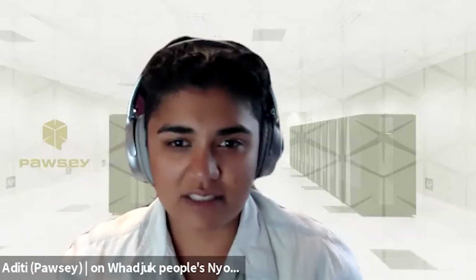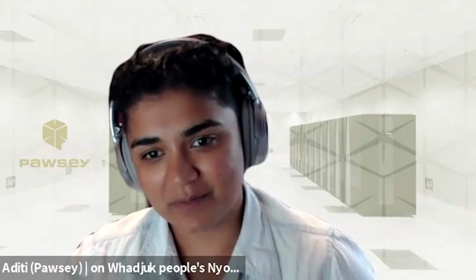Nice. So in this assessment with creating this new data center, do you have any successes or learnings or advice that you have for other centers? Yeah, let me summarize into a couple of points here. First, we have learned and proved that supercomputers do not need to be located on the same campus as the supercomputing center or the university owning it. In the time of very strong networks, we can place the supercomputers where they are most economically and ecologically sensible. The second point, on the brownfield part, is that repurposing existing buildings instead of building new shiny data center buildings is a very cost and eco-efficient way of doing it.